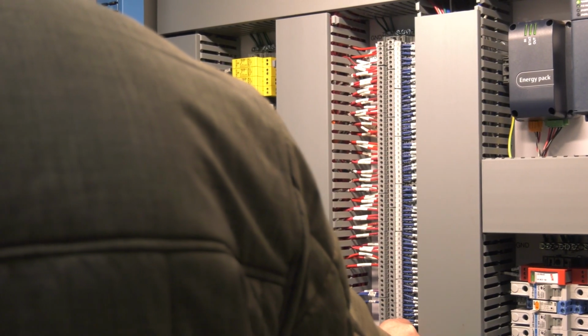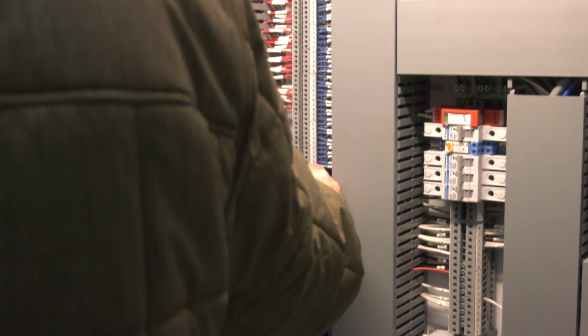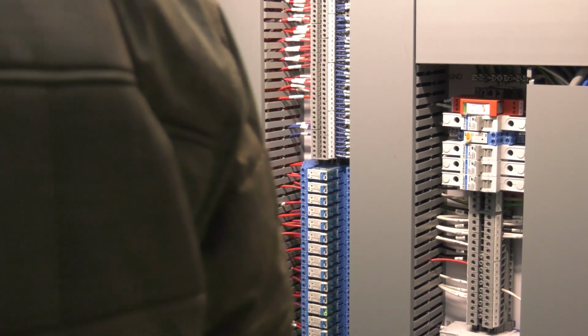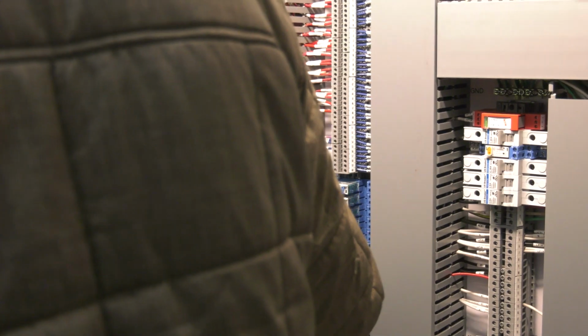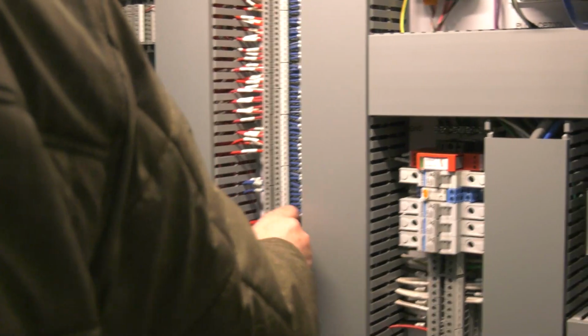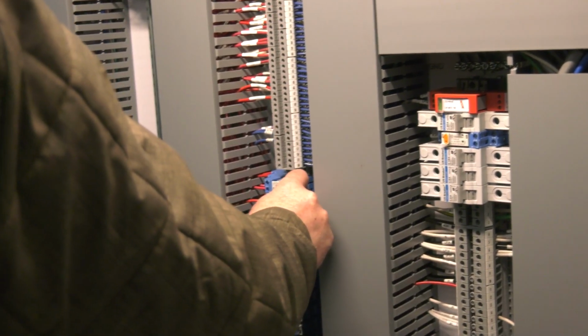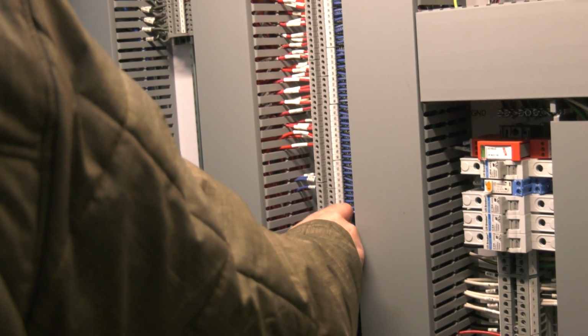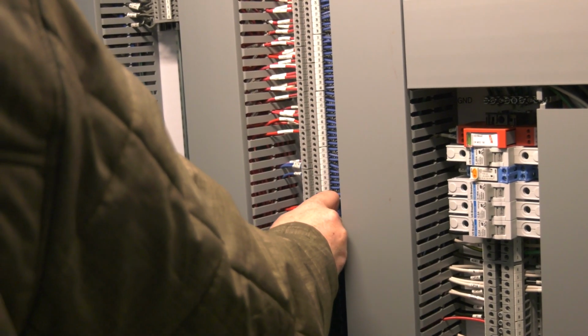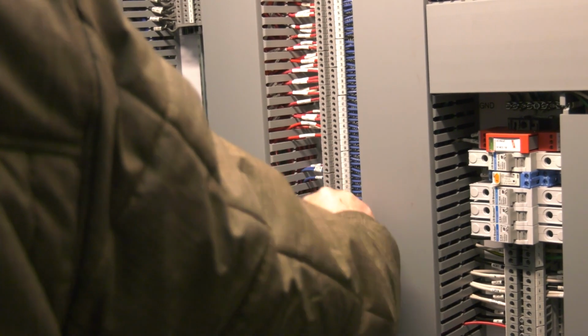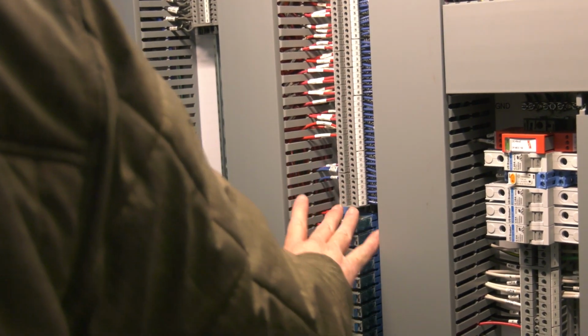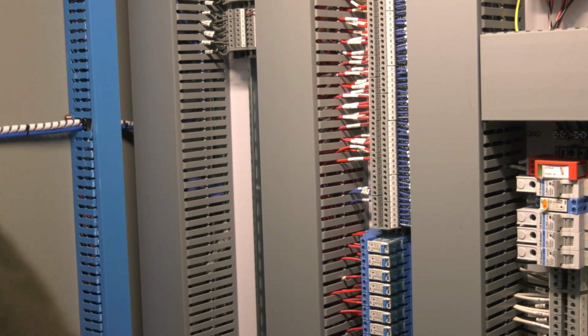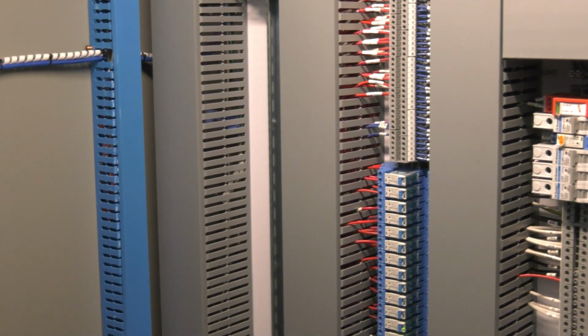And again, with the relays right here, you can press. We were talking about opening a gate partially. If you go to your drawings, you can find which control relay you need to push in to partially open one. Like I say, you can press it, or there's a little plastic tab right here. You just break that little plastic tab off with your thumb, and then you get a screwdriver and you can turn that flag. When it's turned, it's forced on. Yep. So let's see here.